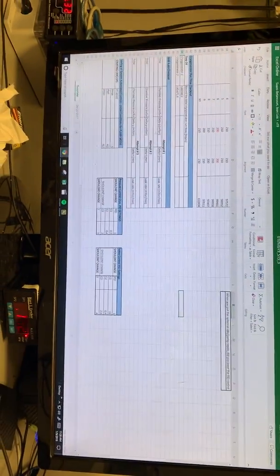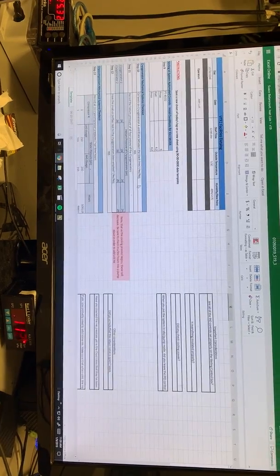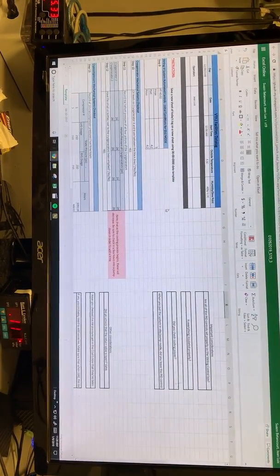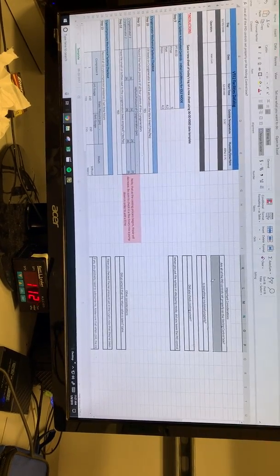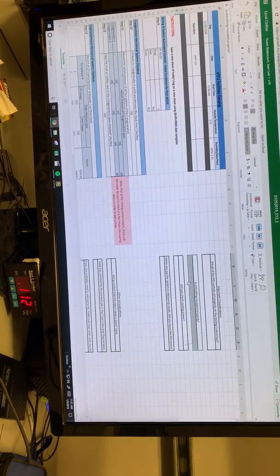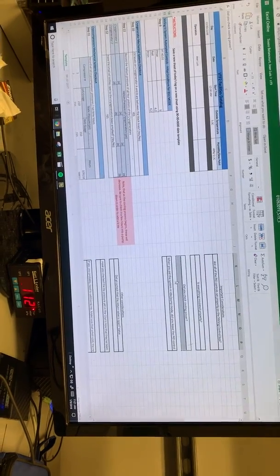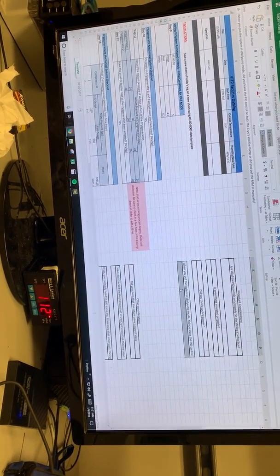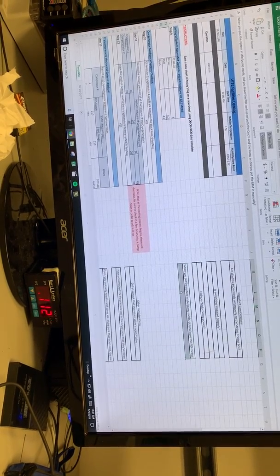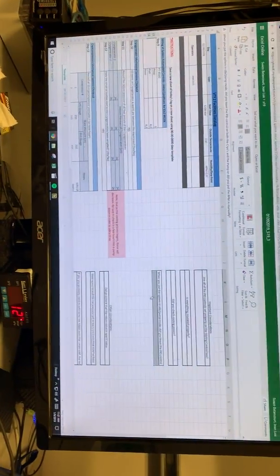Okay, so to this point, you should have completely filled out what is essentially the documentation for the pump down. There's a couple little questions here, like did you set all the PID controls? Are things insulated properly? Did you check cooling power, which is something we're going to do next? And did you set the system into the proper mode? And by system now, I'm talking about the cryo system.